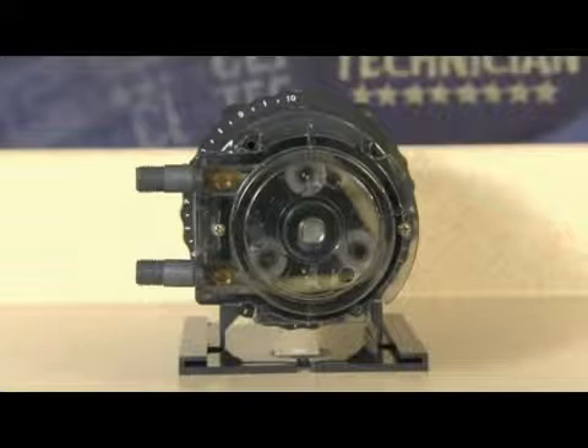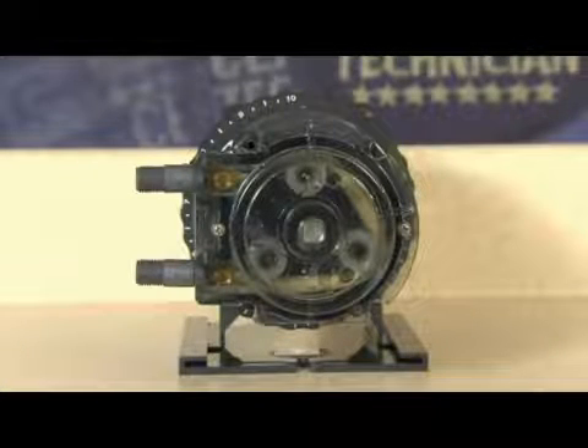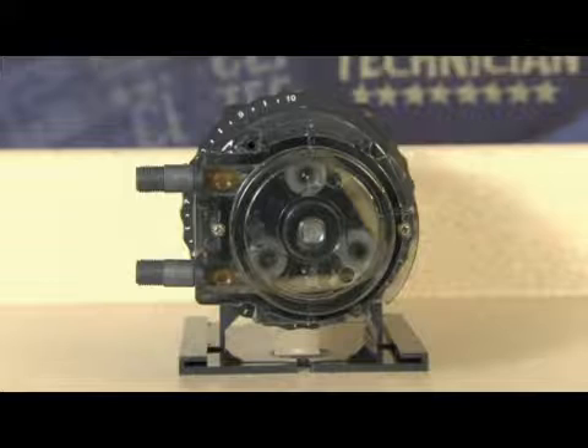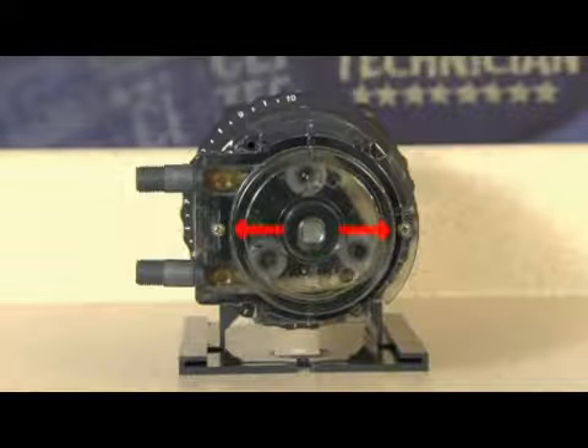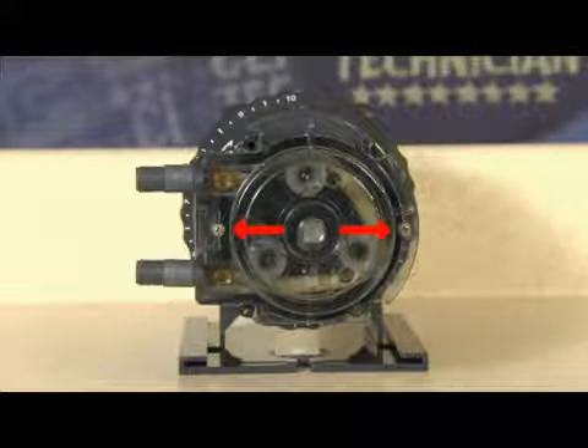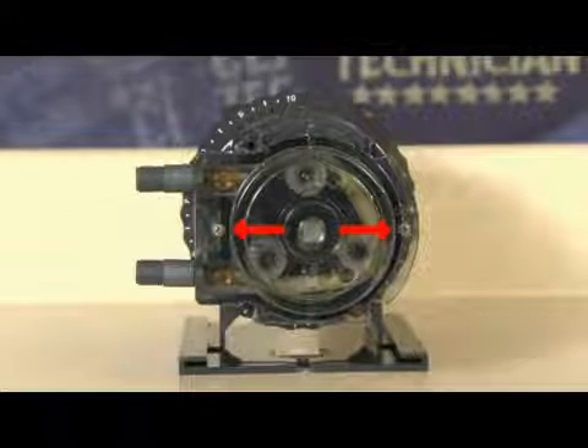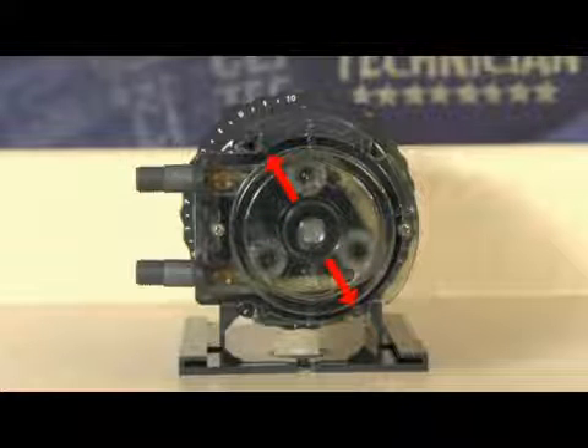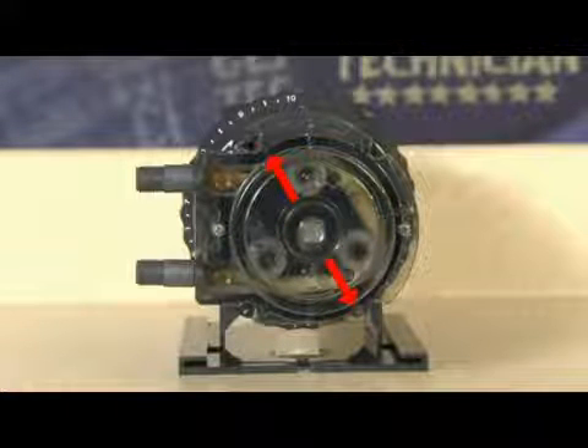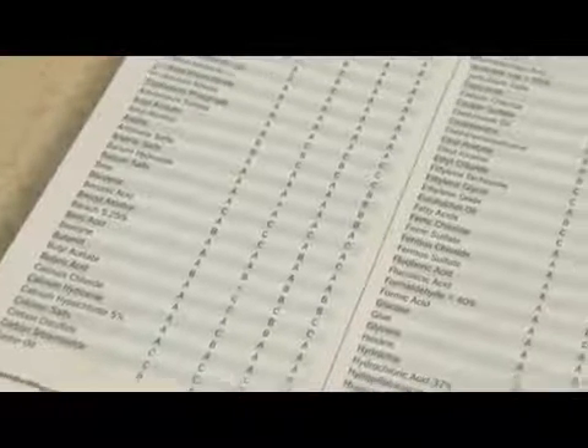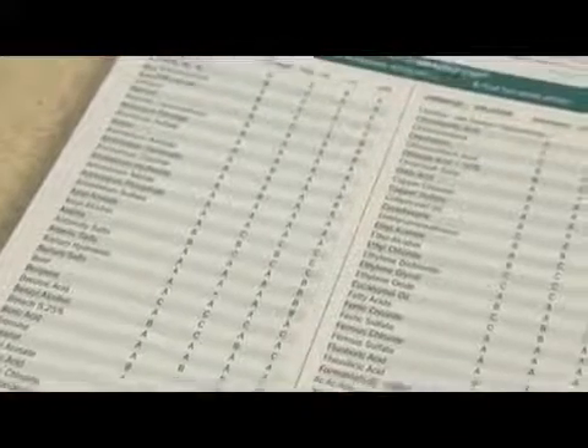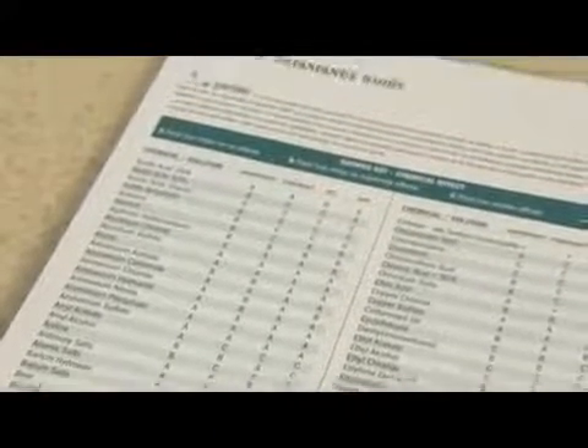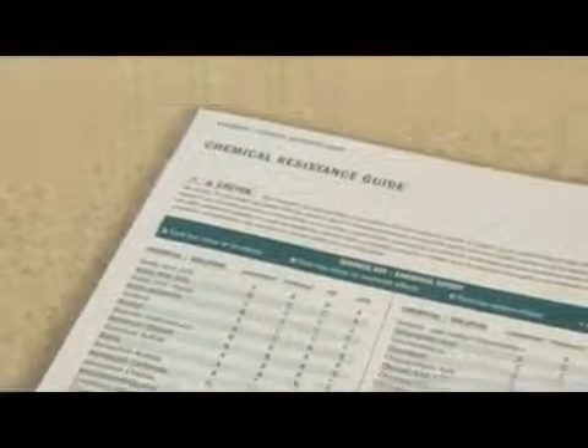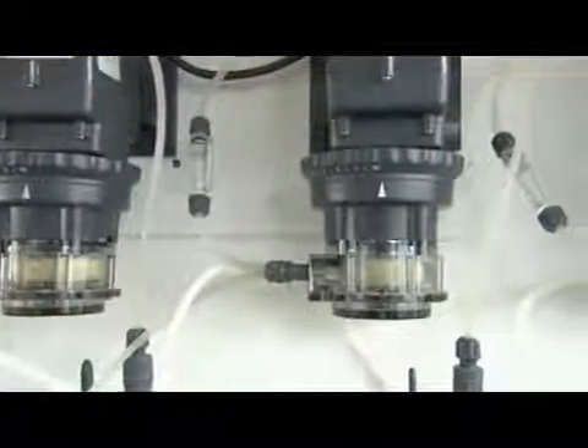Over the course of the pump's service life, the tube housing can crack from wear or from over-tightening the cover screws. 2 self-tapping screws secure the cover. If the screw boss is stripped, select only 2 alternates that are positioned opposite of each other to secure the cover. To address the conditions mentioned, confirm chemical compatibility with the tube housing and pump tube material, which can be different. Review the factory-recommended vertical pump installation.